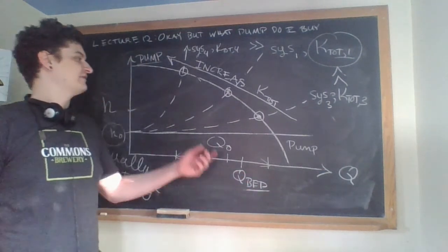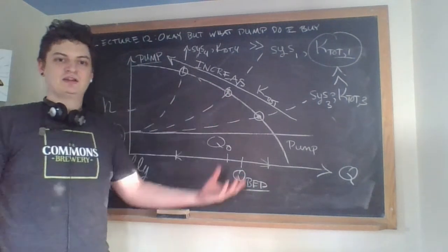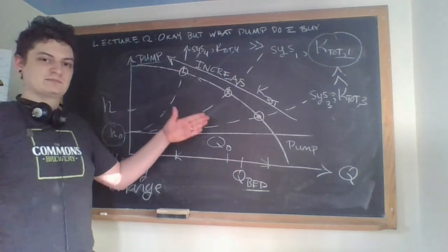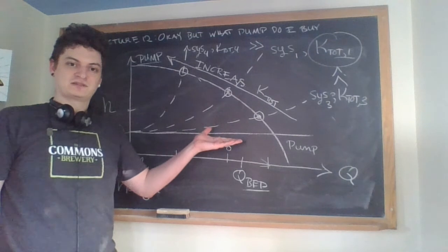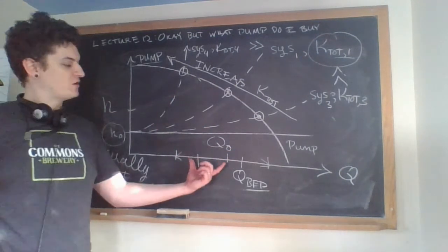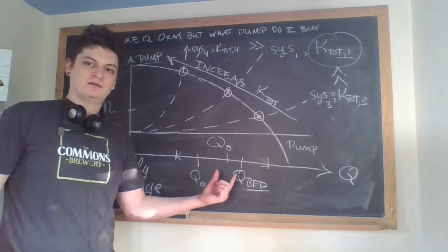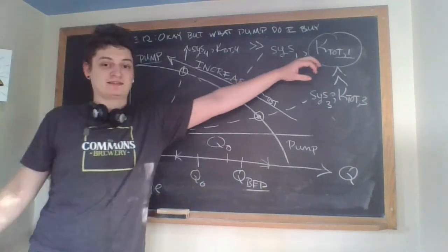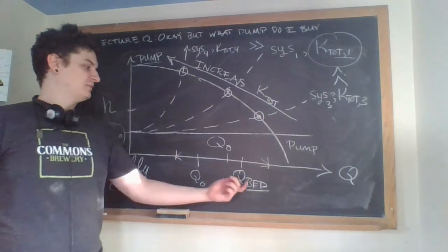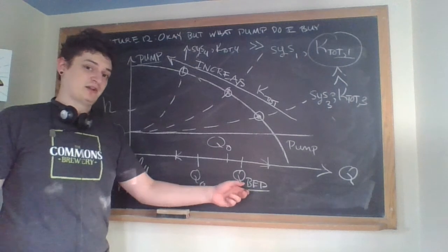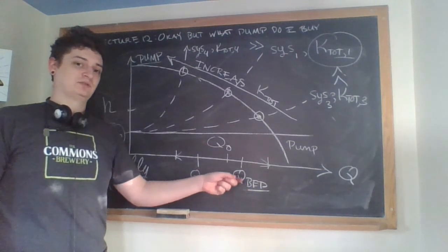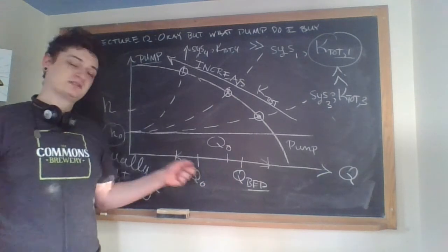So the efficiency graph intersects with the pump curve, giving you a best efficiency point, and then the system curve also intersects the pump characteristic curve, giving you an operating point. And you want these to be close somehow. So you can change maybe designs on here, draw this forward, curl it up, curl it back. This could even be choosing different pumps with different BEPs, looking at tables to get that close to my operating point.